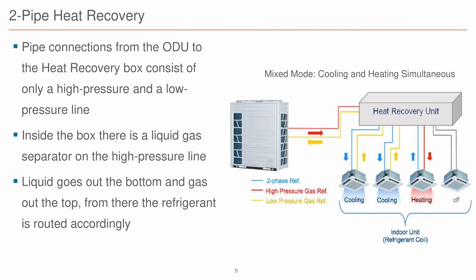You'll notice by these beautiful colors, anybody want to take a guess as to what those 2 refrigerant lines leaving my outdoor unit are? Suction and liquid. Well, they are suction, not really, no. One's labeled high pressure gas and one's labeled low pressure. Yes, high pressure gas, which would be hot gas. 2-pipe heat recovery, it is hot gas and it is low pressure.